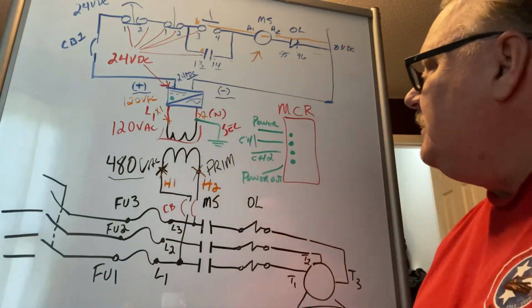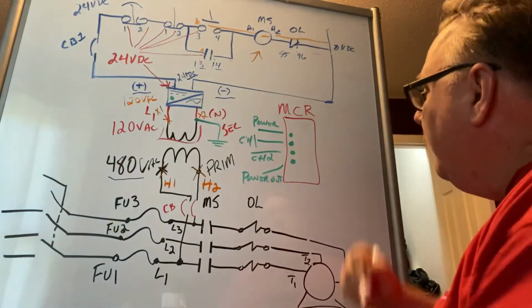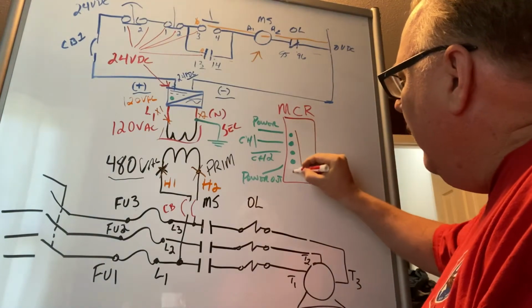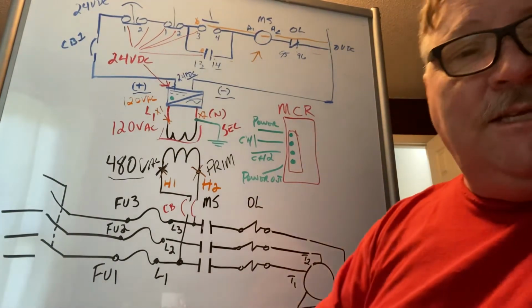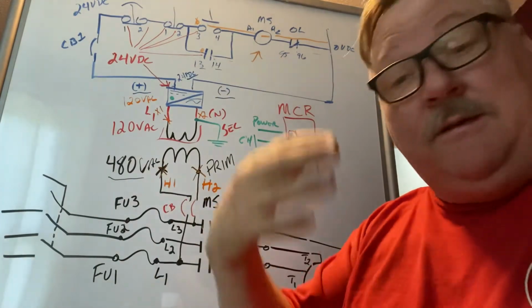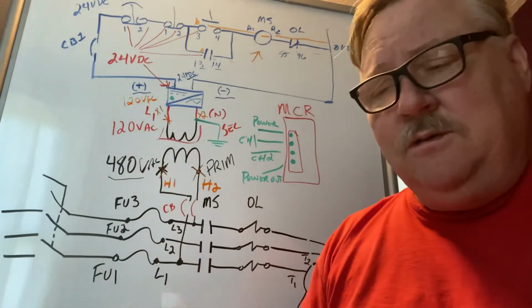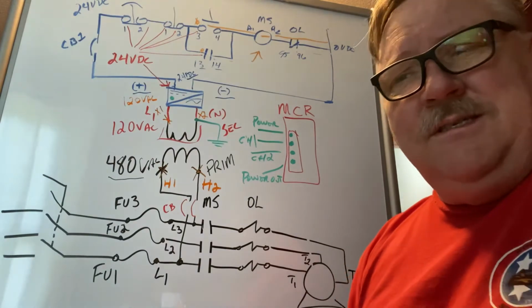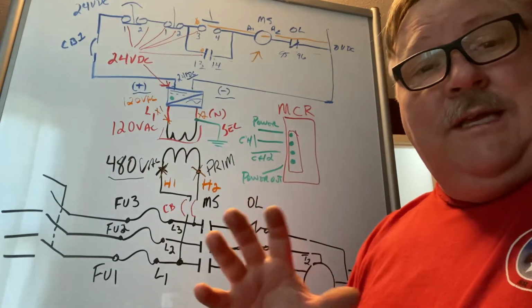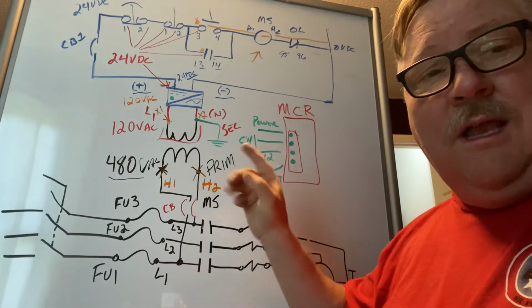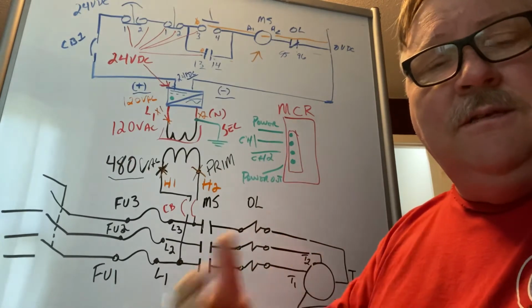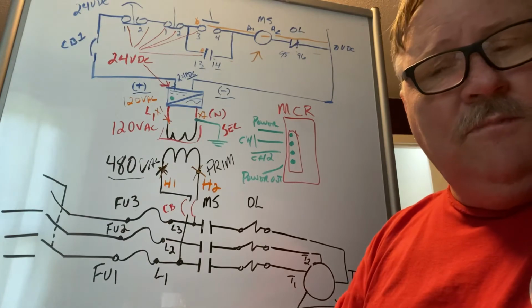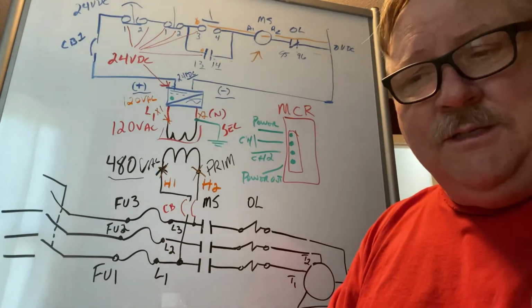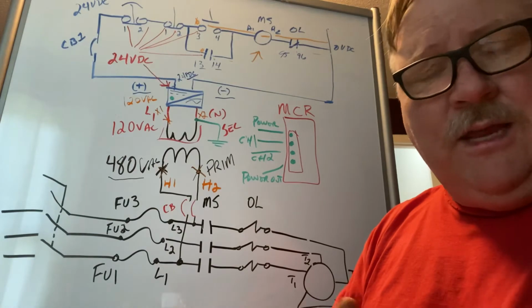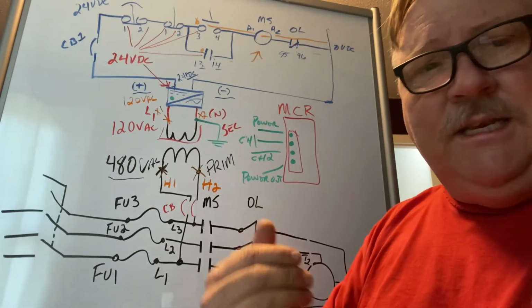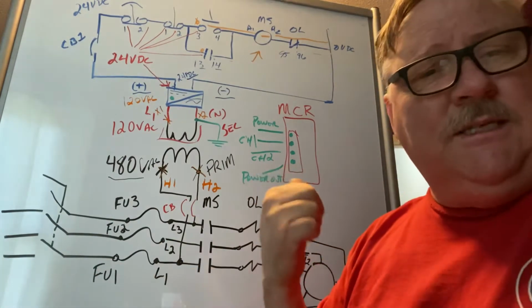When you're looking at this, again, the first thing that you want to look for is your safety relay. And I say 4 green lights. Some of them have 3. Some can have many more, depending on some of these newer ones from Allen Bradley. There's like 5, 6, 7 green lights. But whatever it is, you need to have all of these green lights on. If they're not on, a safety device has been violated. And whether that safety device is a door interlock, a presence mat, a light curtain, an e-stop, any one of those things will cause those lights to not come on.